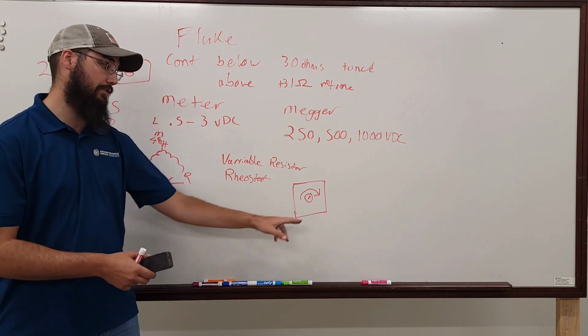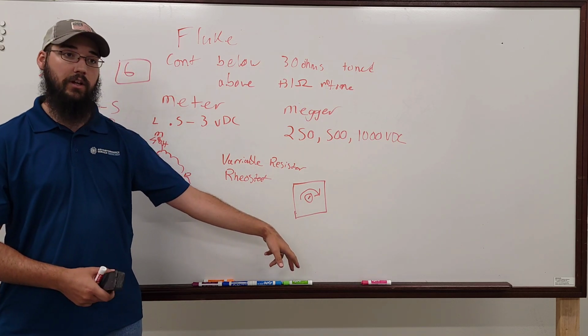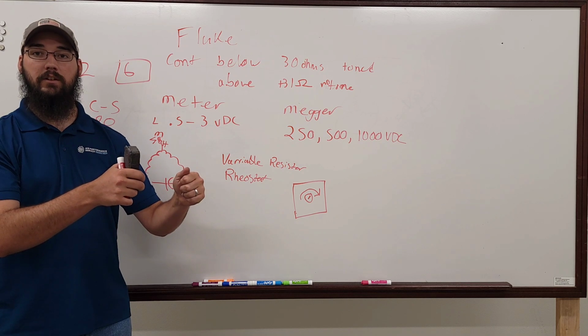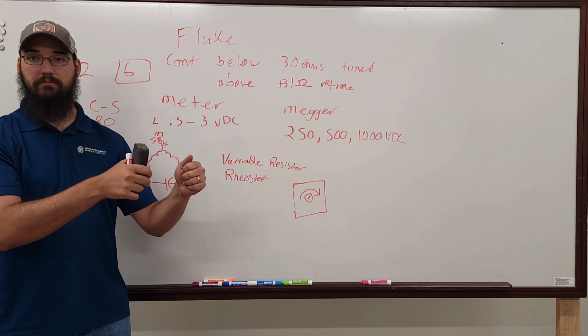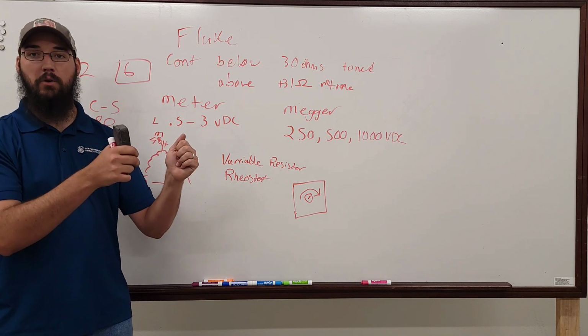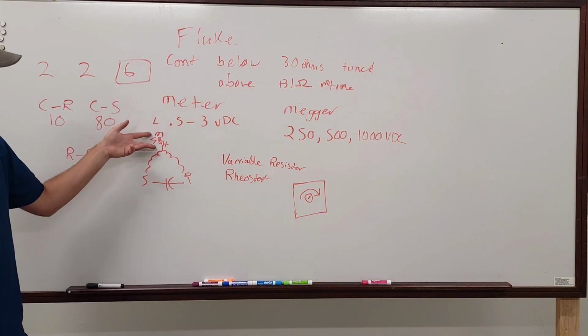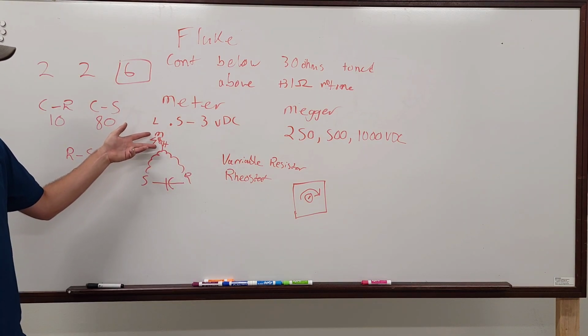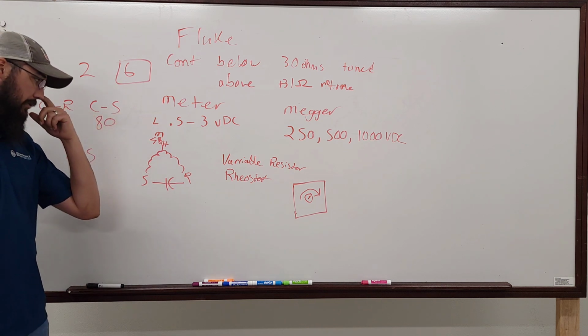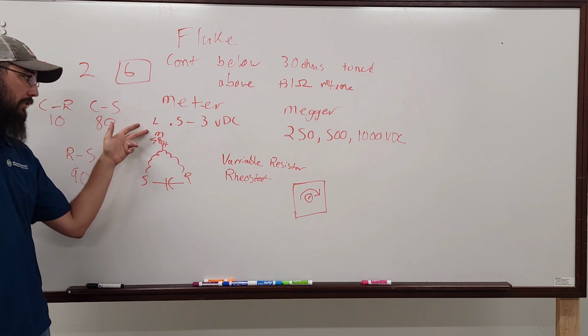That's how you test these. It'll have two wires coming off. You just take your ohms and read across it. You should see X number of ohms. If you don't see anything, the motor won't turn on, and that's probably your problem. That's part of what you can test.